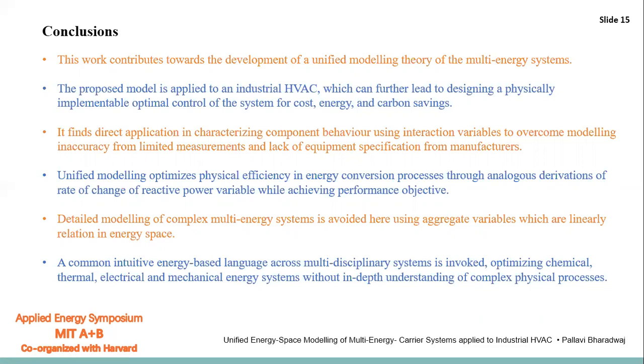It finds direct application in characterizing components which have limited information in terms of measurements or equipment specifications from manufacturers, which is typically the case in industrial equipment. You are not allowed to really get into the system and take measurements out — these are typically closed systems. But just with limited measurements, we've been able to model the system, as you can see.